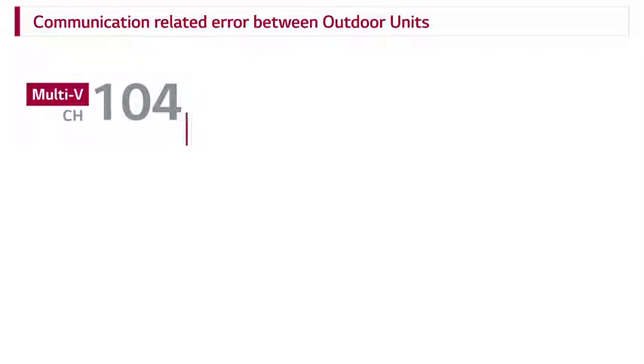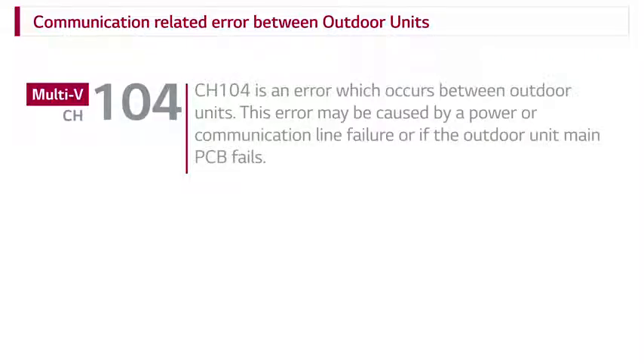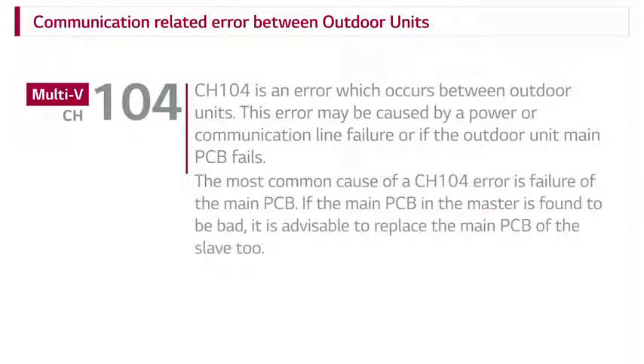Communication related error between outdoor units. CH-104 is an error which occurs between outdoor units. This error may be caused by a power or communication line failure, or if the outdoor unit main PCB fails. The most common cause of a CH-104 error is failure of the main PCB.